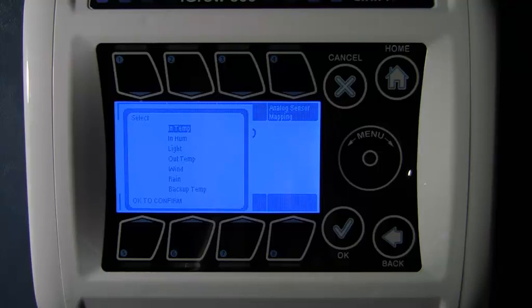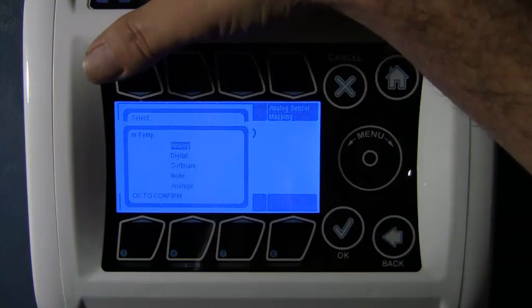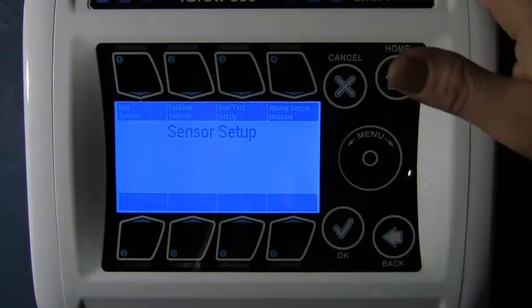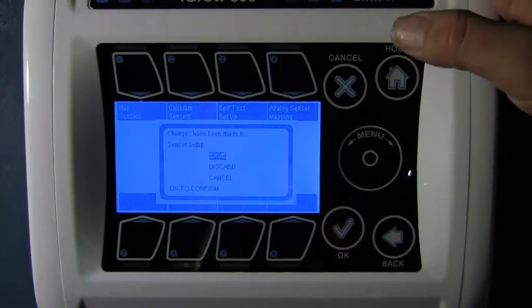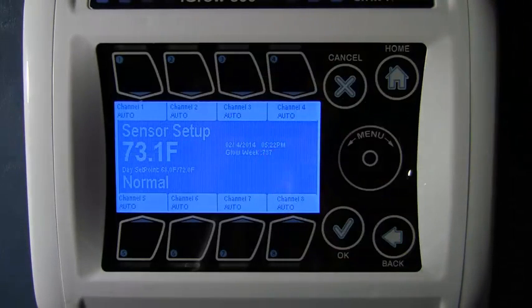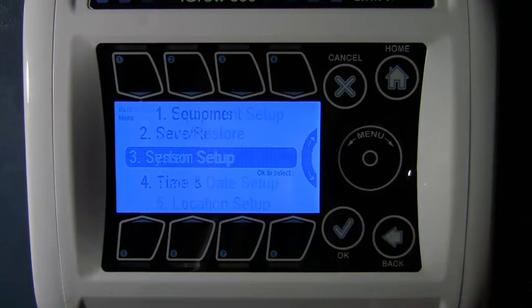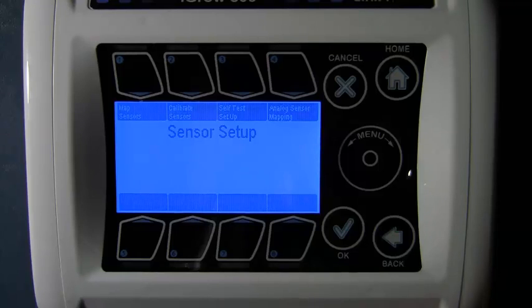If you're going to use an analog probe to measure the inside temperature, make sure that you assign the analog probe to be analog and then hit OK. And if you were to hit Home and save, notice that now you have a sensor reading because the analog probe is hooked up, it is now mapped, and now you have a sensor reading displayed here at the main screen. Let's go back into the sensor setup again, and let's go ahead and talk about calibration.